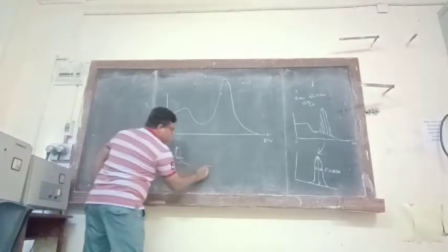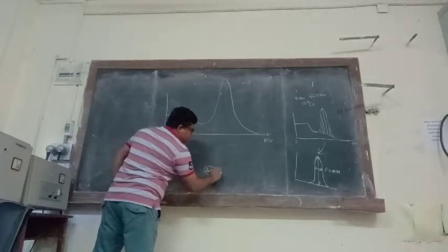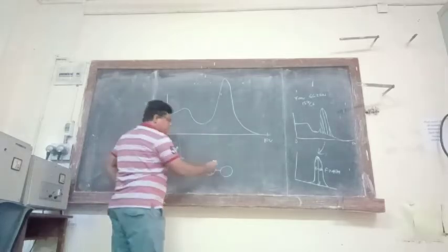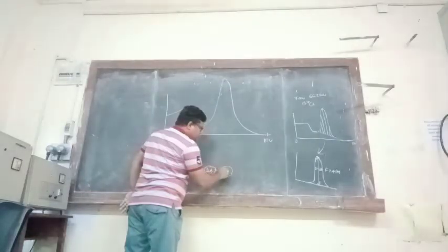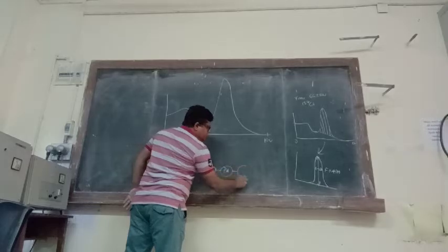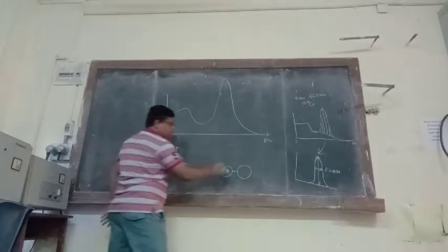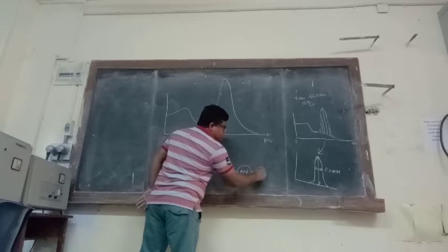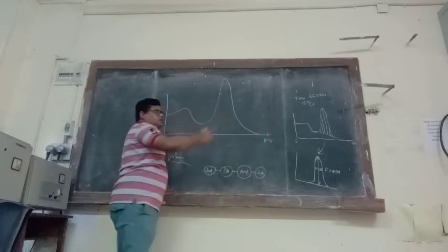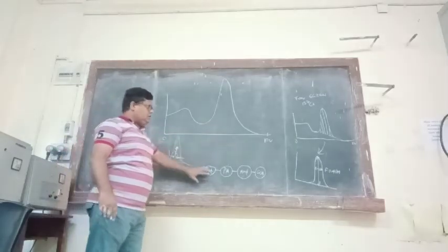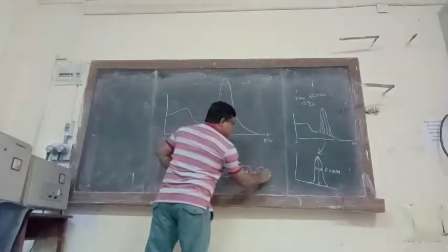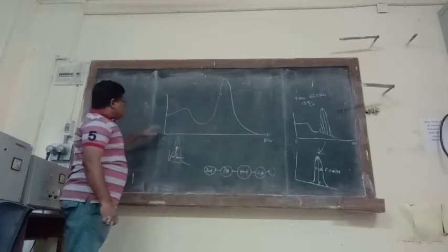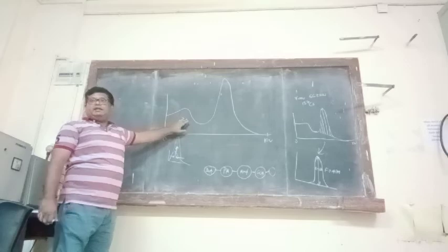So first we have the detector, then a coupling instrument which does impedance matching between detector output and after-load electronics. This is the pre-amplifier. Next we have the amplifier, and then your single channel analyzer or discriminator, which does the scanning part. So this is the overall chain, four very important parts. After that, of course, we have the scaler and counter, which counts. This should be your ideal measurement.